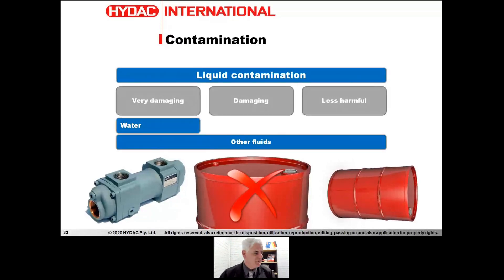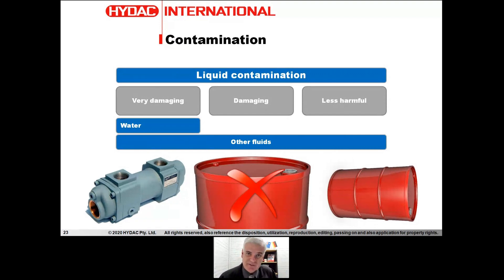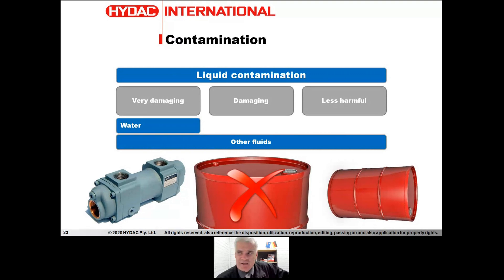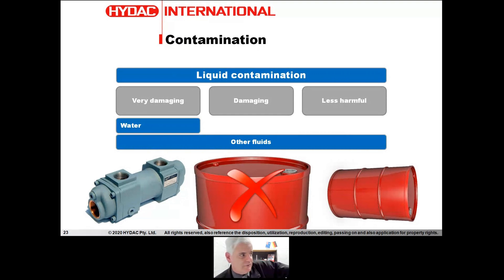As a rule of thumb, if storing drums outside, try to put them on their side. If you align the bungs horizontally, you're not exchanging air out of that drum and it keeps the lubricant drier. Other fluids can be contaminants too — ranging from very damaging to less harmful depending on how much mixing is occurring and what the other fluid is. For example, engine oil getting in through a damaged shaft seal — or people simply thinking 'it's just oil, it's all oil, mate,' and topping up a hydraulic system with engine oil. These practices make a very big difference.